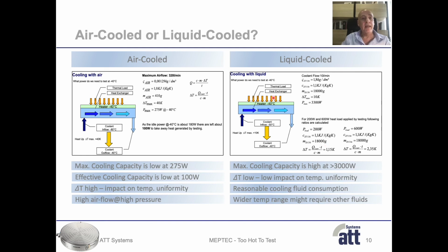So again, the heat dissipation process is the same. Due to the high density of the thermal fluid, we can set the coolant inflow temperature to minus 50 degrees C, and the coolant outflow temperature is again minus 40 degrees C, and it cannot be higher. And this gives us a delta T of 10 Kelvin. So let's quickly do the calculation here. With the given density and the coolant flow rate of 10 liters per minute, we can calculate the thermal mass with 18,000 grams. And this is more than 40 times higher compared to the air-cooled system.